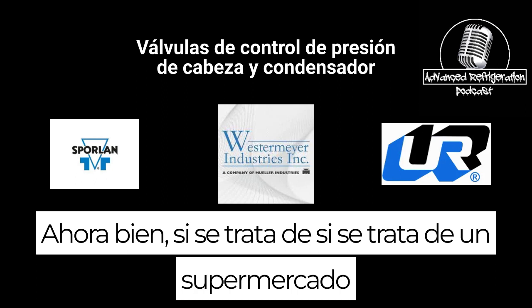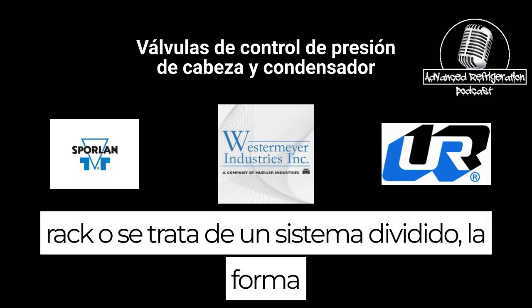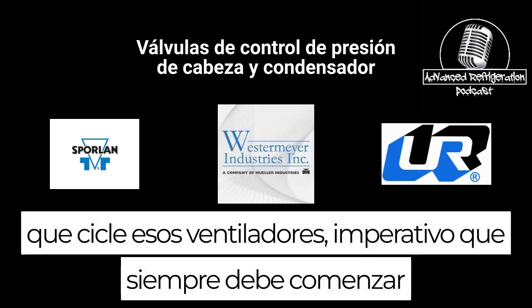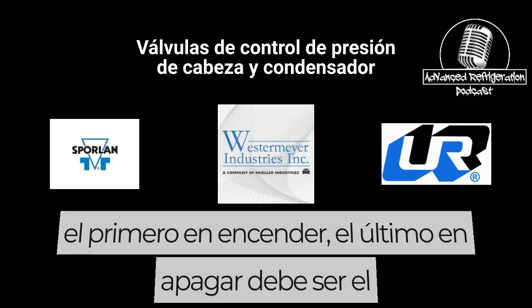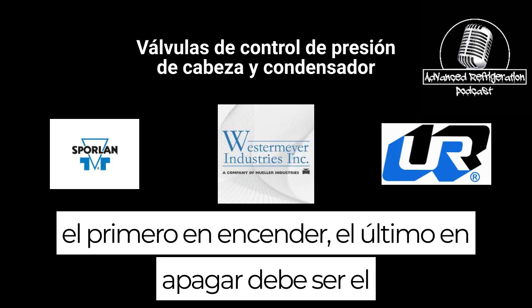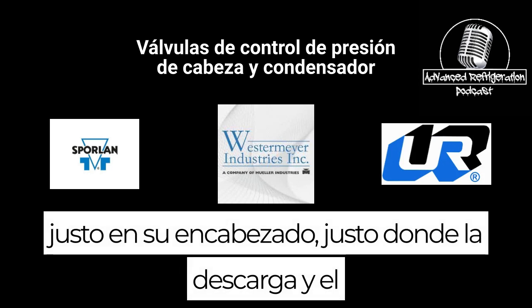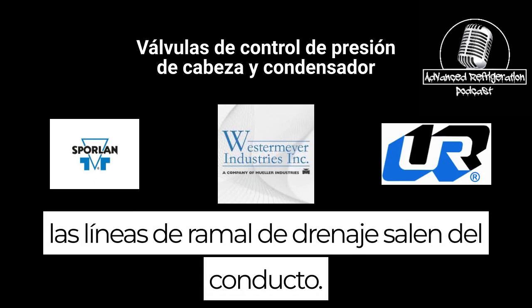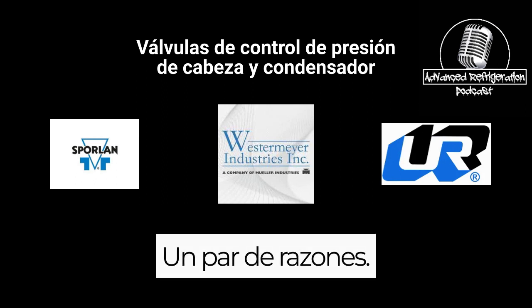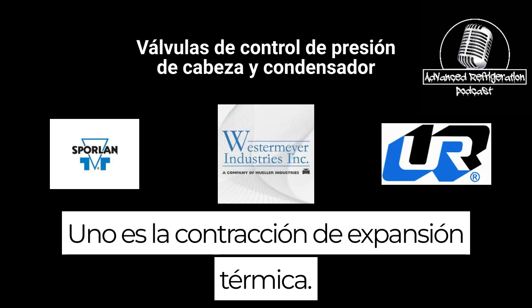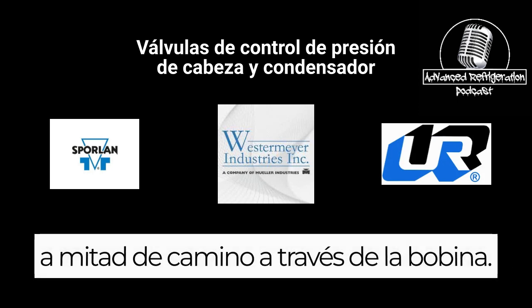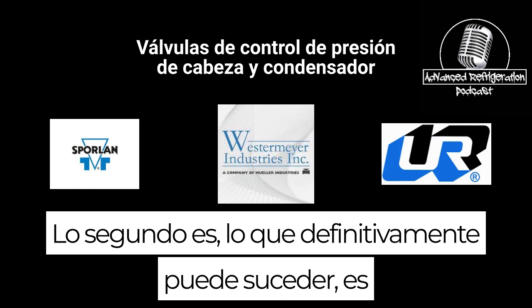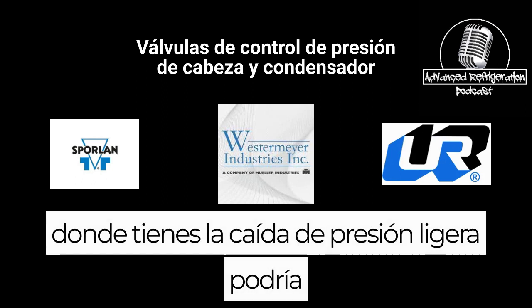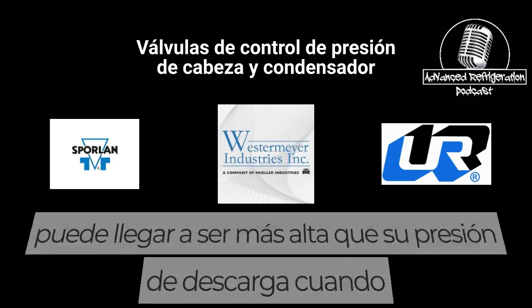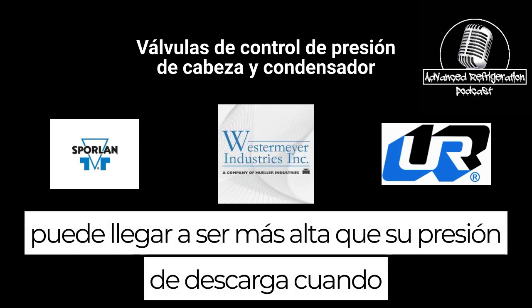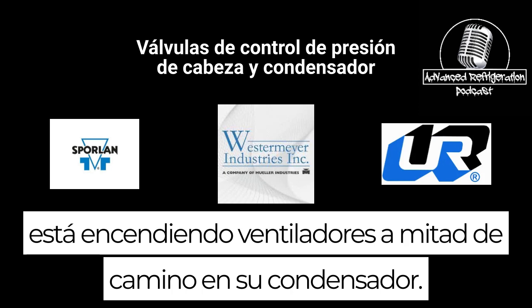Now, whether you're dealing with a supermarket rack or a split system, the way that you cycle those fans is imperative. You should always start first one on, last one off should be the one right at your header, right where the discharge and the drain that your drop leg lines leave the condenser. A couple of reasons. One is thermal expansion and contraction. You don't want to be heating midway up through the coil. Second, which can definitely happen, is that the drop leg pressure could potentially get higher than your discharge pressure when you're turning fans on midway in your condenser.